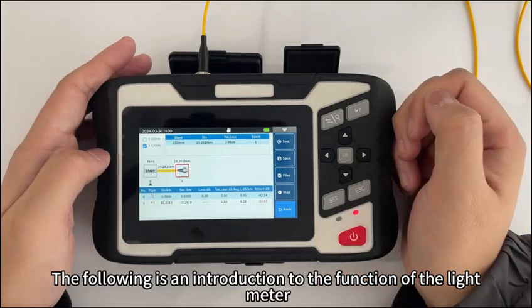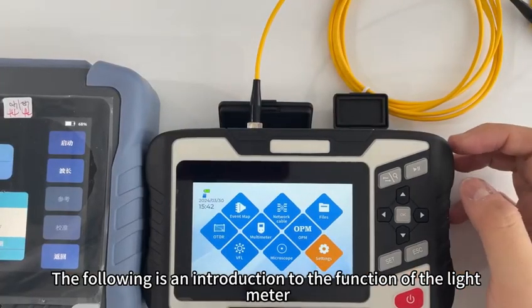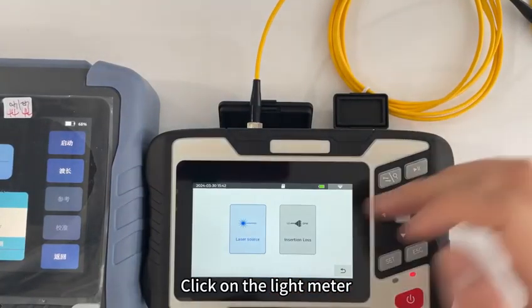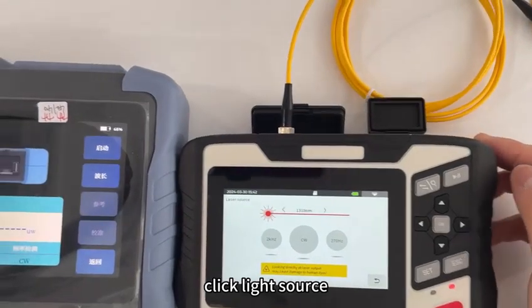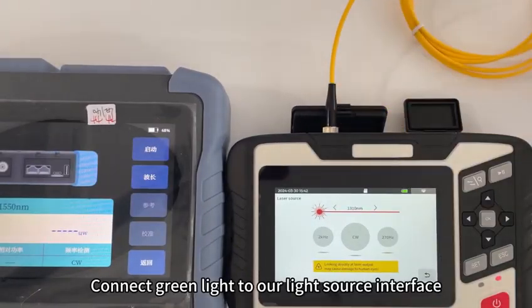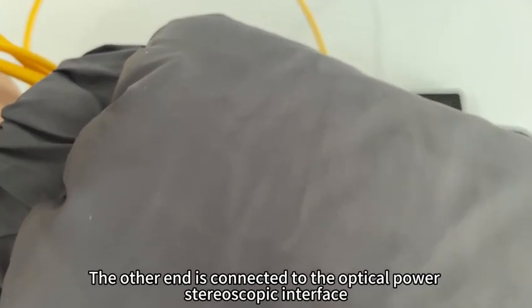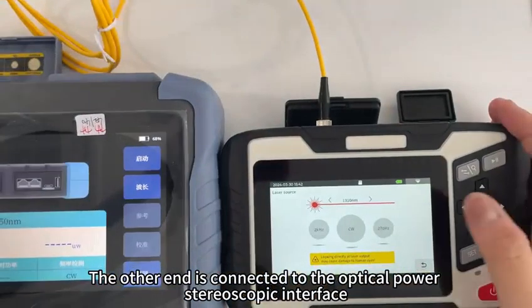The following is an introduction to the function of the light meter. Click on the light meter. Click the light source. Connect a jumper to our light source interface. The other end is connected to the optical power meter interface. Turn on the light source.